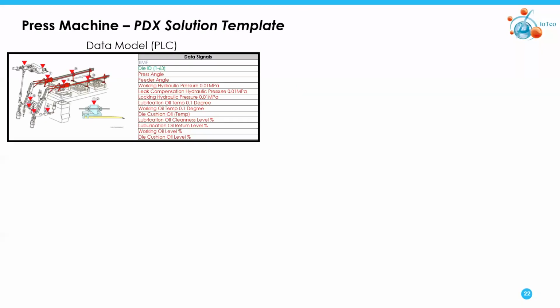This is the data model. There are different approaches to connect to a stamping press. Here is a more non-intrusive data model. We did not need any sensors mounted on the machine. We just needed specific information around primarily the angle, the pressure, the temperature, and oil levels, and those three or four parameters were quite sufficient in this example. To do more, vibration sensing may be required on critical areas of the machine, but we typically start in this non-intrusive way and just capture data from the PLC.